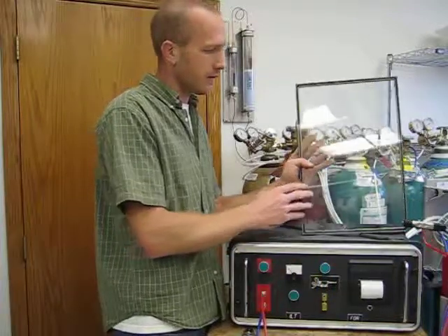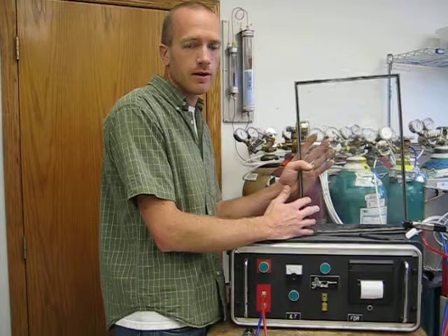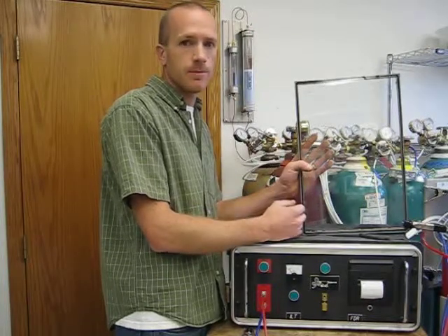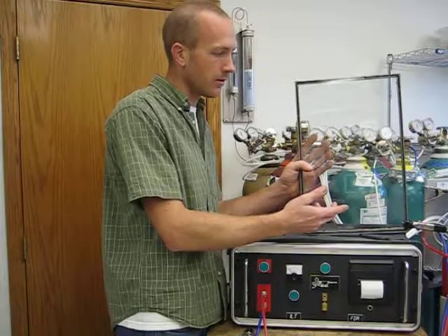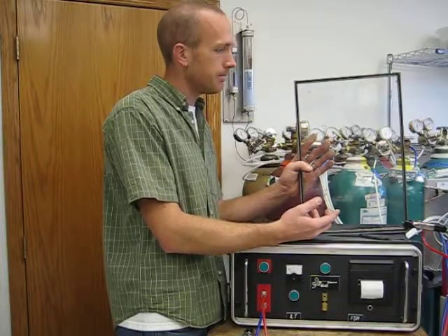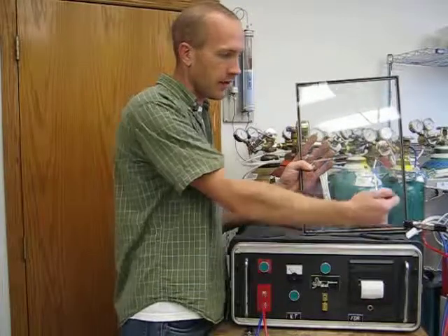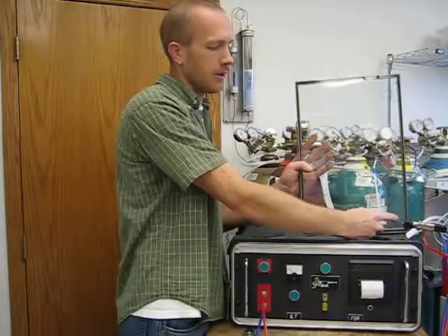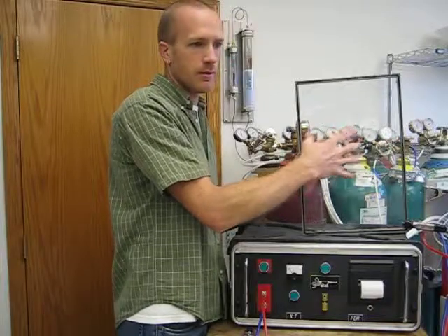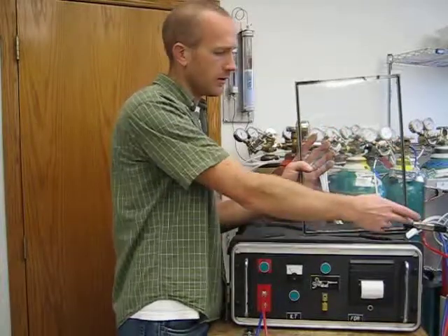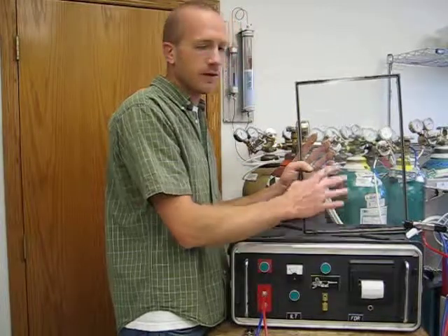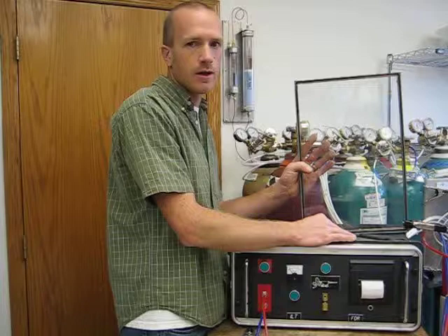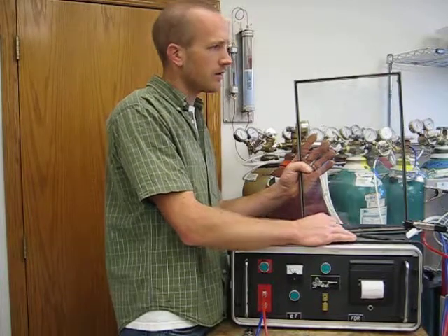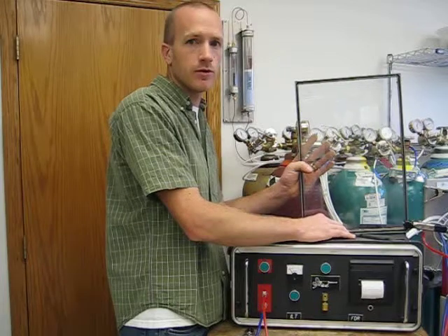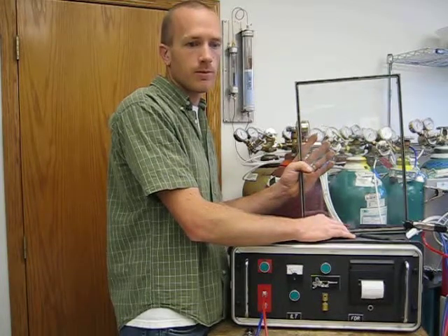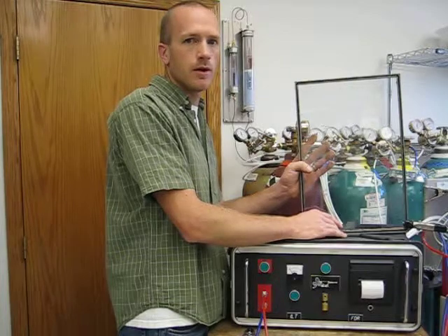How long it takes to test a particular unit depends basically on the size of the unit, and we can also set the machine up for two lances. So there's one in the top and one in the bottom. That would probably mix up the gas a little faster than using the one hole filling method. So time to test the unit is going to be about 1 to 3 minutes. It's not a whole lot of time, and since you're not going to be testing every unit that you produce, the test time is going to be pretty minimal overall throughout the day.